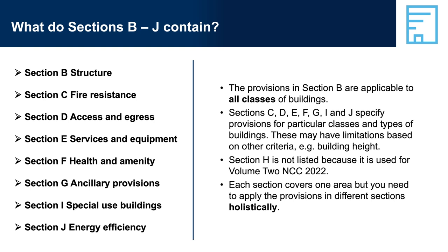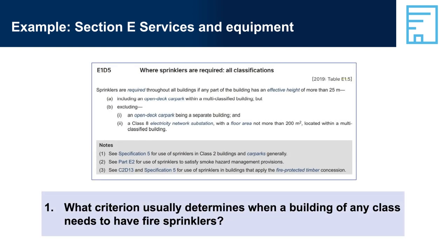Check each section to make sure you understand how it is organised. Example — Section E Services and Equipment, Question 1: What criterion usually determines when a building of any class needs to have fire sprinklers? One trigger for when a building is required to have fire sprinklers installed is when the building has an effective height of more than 25 metres. Effective height means that any part of the building is above that height. However, subsequent clauses including E1D6 to E1D13 may also have other triggers for fire sprinklers, additional requirements or exclusions.